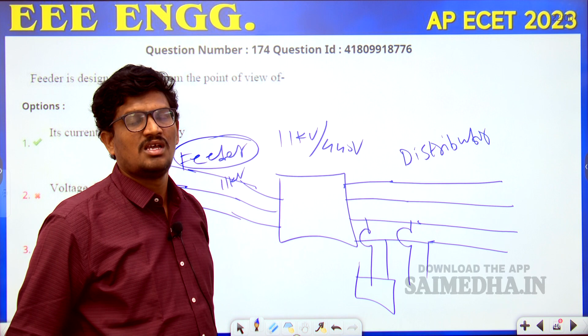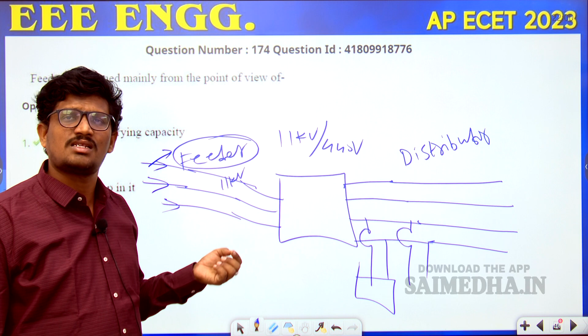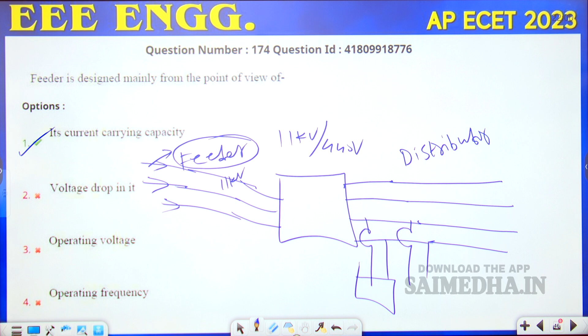These two points are very important: the distributor has tappings, the feeder has no tappings. Since there are no tappings in the feeder, the flow of current from input to output remains the same. That's why the feeder design depends upon current carrying capacity—so option 1, current carrying capacity, is the right answer. Voltage drop is based on the distributor; operating voltage and operating frequency are not correct.